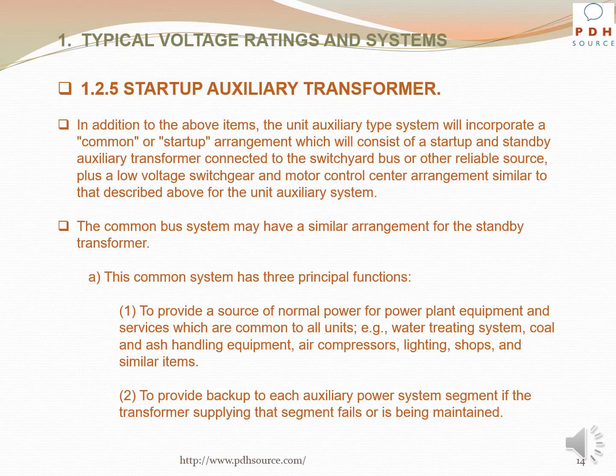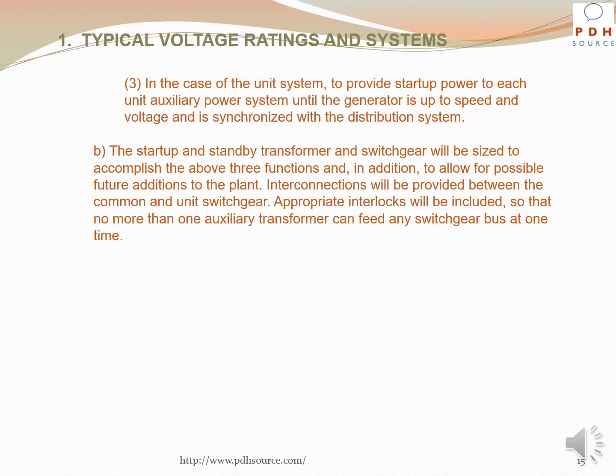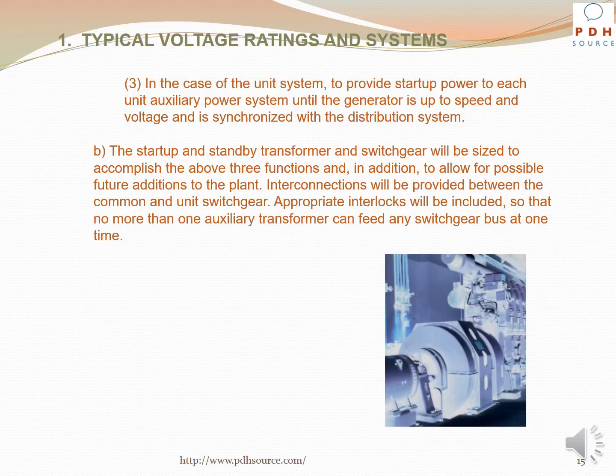This common system has three principal functions: to provide a source of normal power for power plant equipment and services which are common to all units, such as water treating system, coal and ash handling equipment, air compressors, lighting, shops, and similar items; to provide backup to each auxiliary power system segment if the transformer supplying that segment fails or is being maintained. In the case of the unit system, to provide startup power to each unit auxiliary power system until the generator is up to speed and voltage is synchronized with the distribution system.